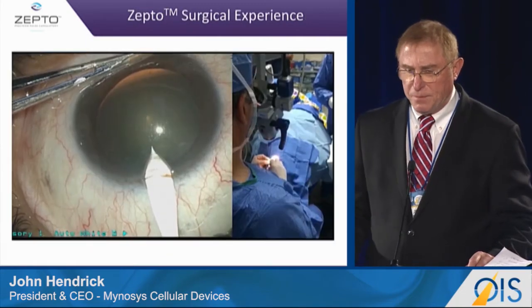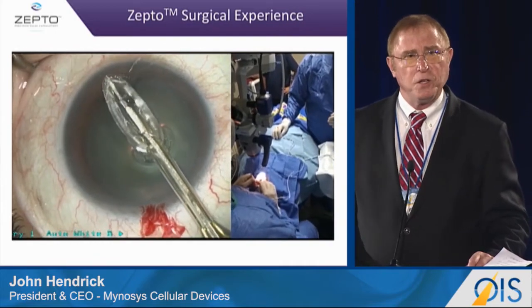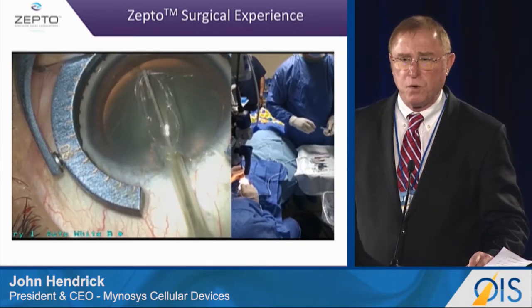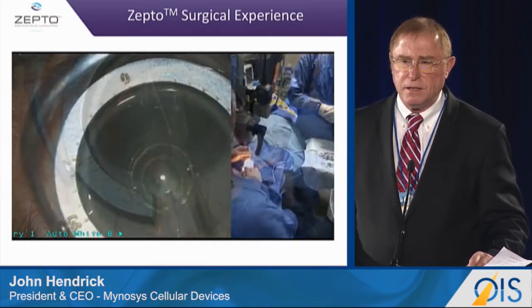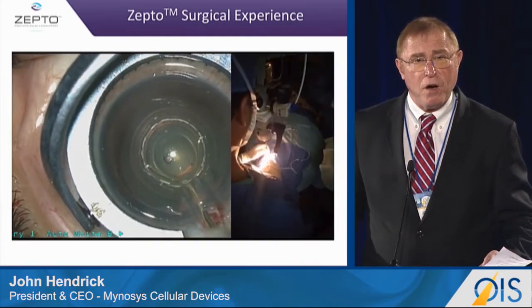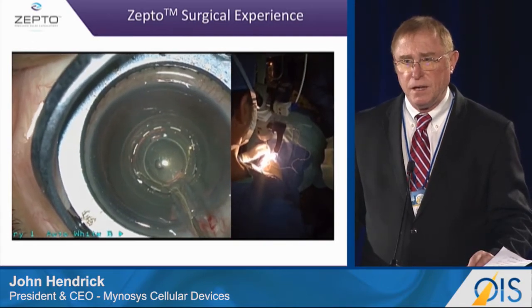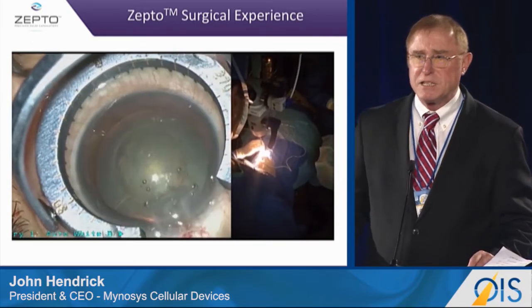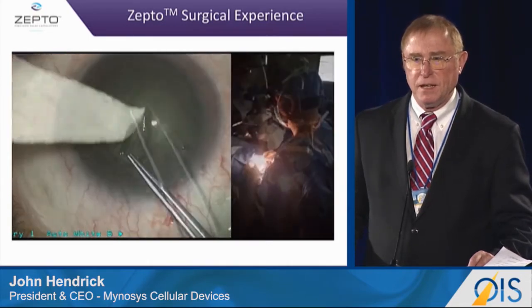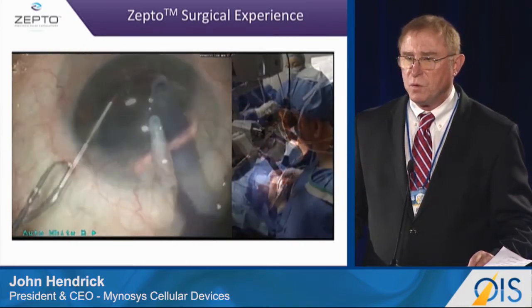What we see today is a video, because I could sit up here and talk to you about how good Zepto is, but I would rather show you. Here is how the device works. It is elongated with a push rod. It is centered on the visual axis intraoperatively. A mild suction is developed, and then in four milliseconds, energy is delivered simultaneously. And here you have a perfect capsulotomy centered over the visual axis.